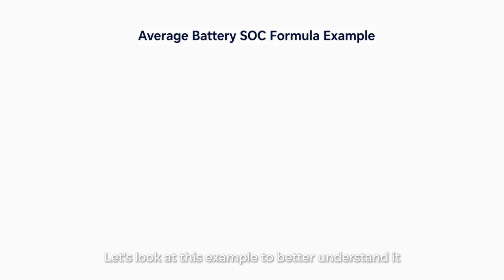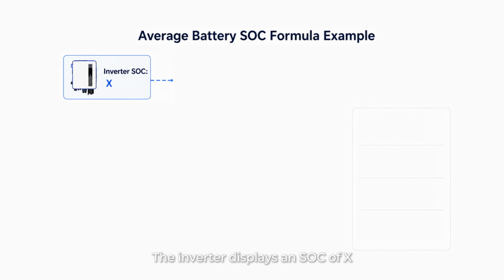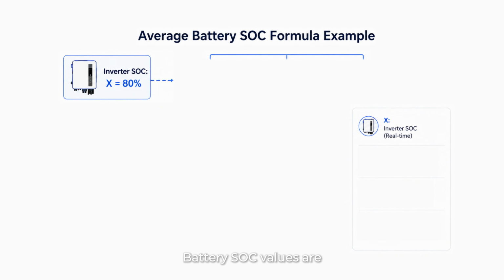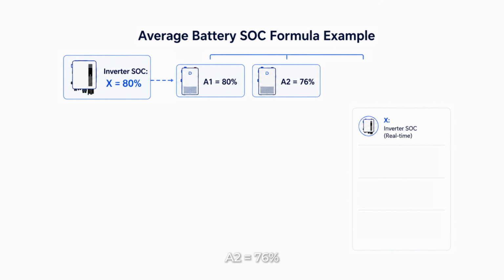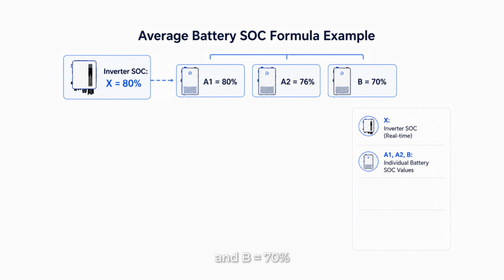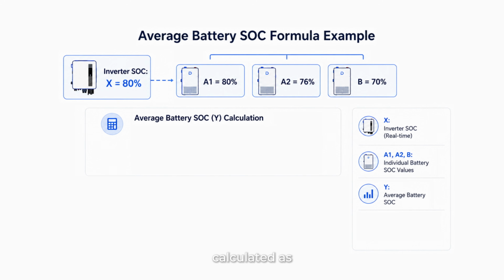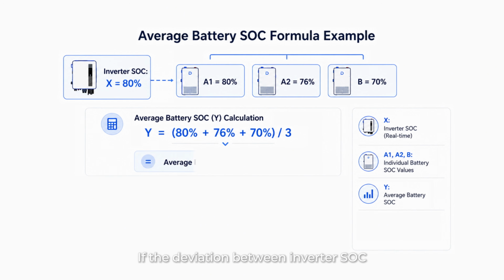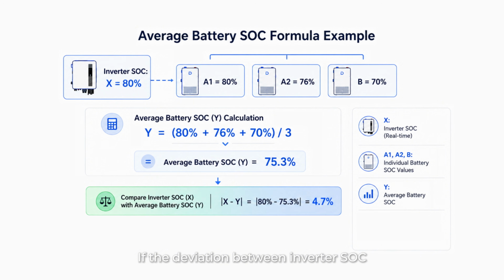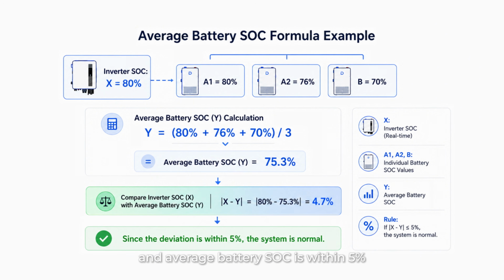Let's look at this example to better understand it. The inverter displays an SOC of X, where X equals 80%. Battery SOC values are A1 equals 80%, A2 equals 76%, and B equals 70%. The average battery SOC is Y, calculated as Y equals (80% plus 76% plus 70%) divided by 3. If the deviation between inverter SOC and average battery SOC is within 5%, the system is normal.